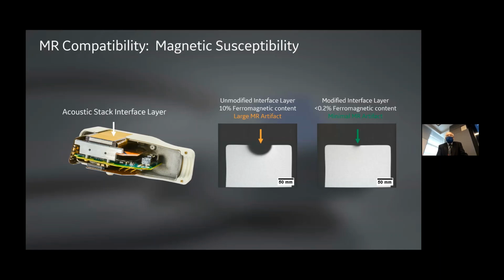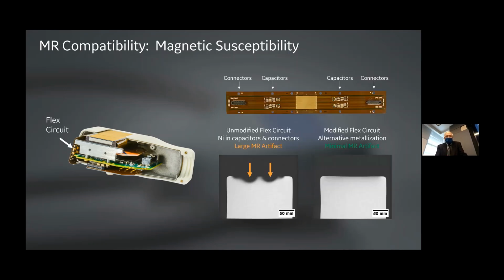One of the big ones turned out to be one of the interface acoustic matching devices that we had in the transducer array, which had a relatively large amount of ferromagnetic content, although you wouldn't necessarily expect that based on what its name is. We found a way to make that material without so much ferromagnetic content and change it a little bit. So you can see the difference between burning a big hole in your image and having pretty close to no impact. The other big one had to do with the flex circuits that we built. The ordinary way of making flex circuits includes a fair amount of nickel in the way the traces are built up, as well as in some of the components in them. And so you go work with manufacturers to get rid of those things as well.